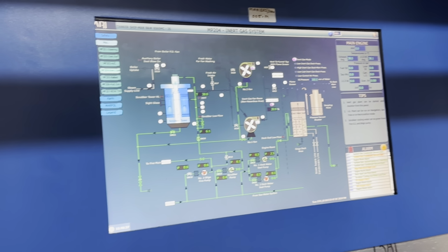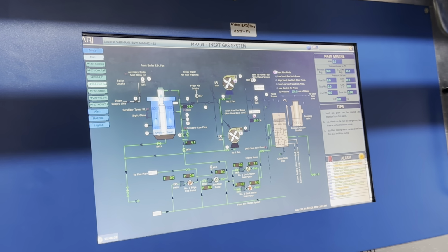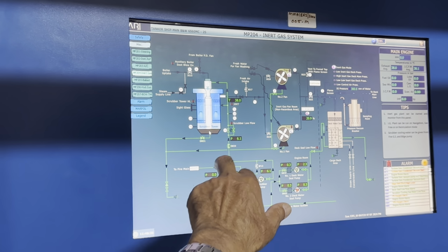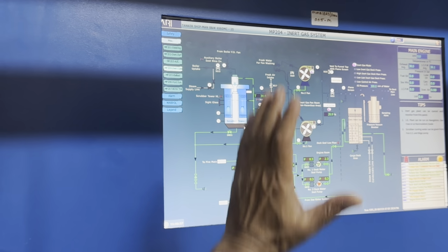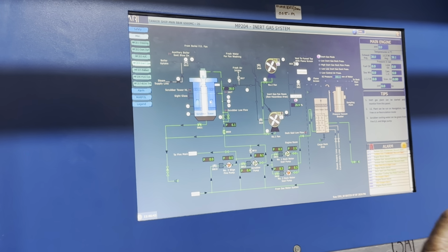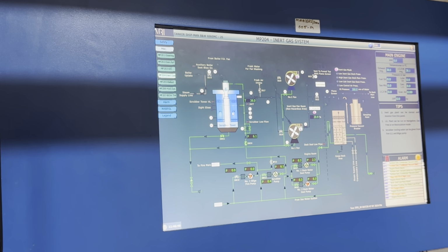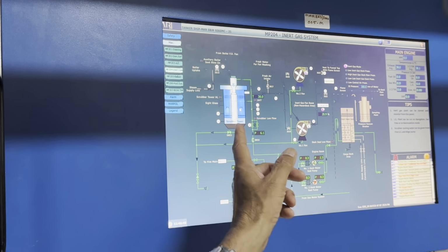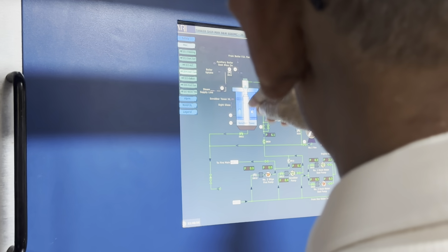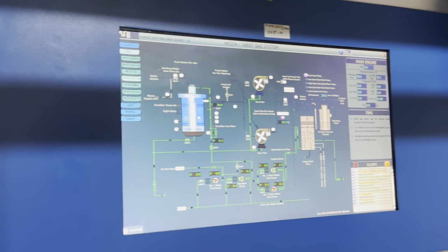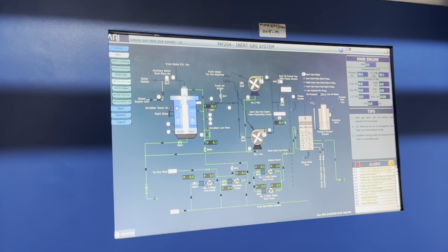So IG comes in from the bottom, because it cannot push the water. We are maintaining this much water, the head it cannot push. So it goes up, and this is a packed bed of irregular shapes, like triangular pieces or small balls. The IG passes through in a zigzag, touching those objects, while the water is sprayed there. So it is washed, scrubbed and cleaned. And the demister is on top.